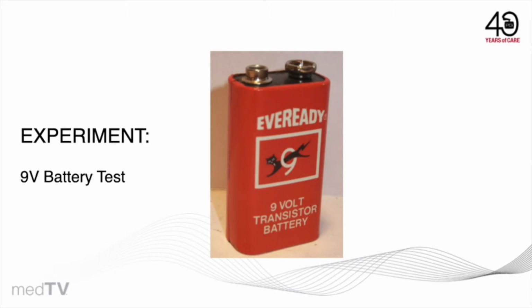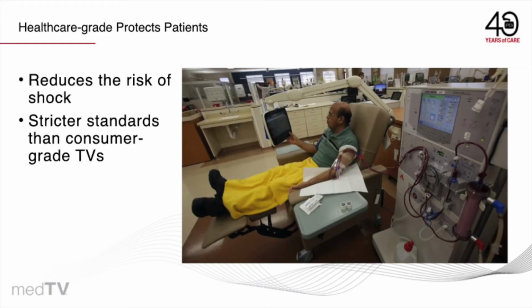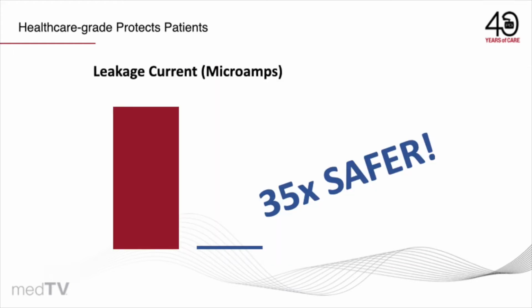In the consumer market, that's great. Most of us don't go around with IVs or pumps or anything into our bloodstream in a home market. But when you get in healthcare, often that skin barrier is broken. It's got an IV in it, or it's got other devices into your skin. So the healthcare standard is much more stringent than a consumer standard. For example, the consumer market can have up to 3,500 microamps of leakage current that's acceptable on a television, a radio, a handheld device that you may hold at home. But in the healthcare market, if you can touch it, it has to be less than 100 microamps. So 35 times greater protection for leakage current is required within the healthcare facility on an electrical device.